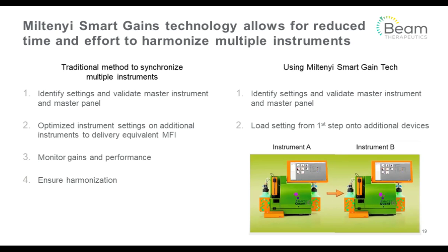So you would only need to identify settings and validate your panel on one instrument. You take all of those settings that you set up and validated from one instrument and take that to any other instrument with a simple USB load, and you can ensure that that same panel will run the same way on the same instrument with reproducibility and confidence. We've really had great success with this with multiple instruments on site and even tech transfers from site to site. So we're big fans of this technology.